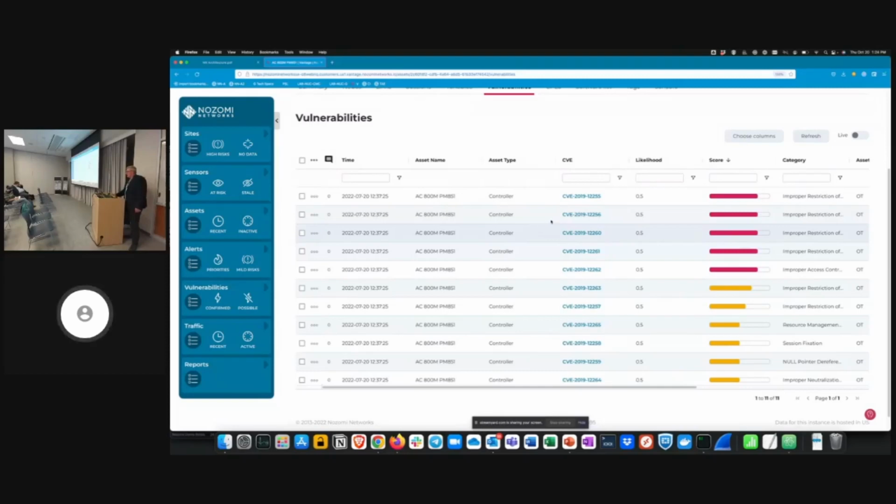Now, patching. Vivek talked about patching in his talk earlier this morning. Unlike the IT world, in OT we tend not to patch these boxes very frequently. Sometimes some of these boxes run proprietary software. Some of the HMIs are running Windows, but they might be versions that we have long forgotten about. Like, I still see Windows XP out in the wild all the time, right? Because that's how the vendor built their system. If you try to upgrade that to Windows 10, first of all, the hardware probably wouldn't support it, and second of all, it would probably break all the software that they built 20 years ago for these systems.